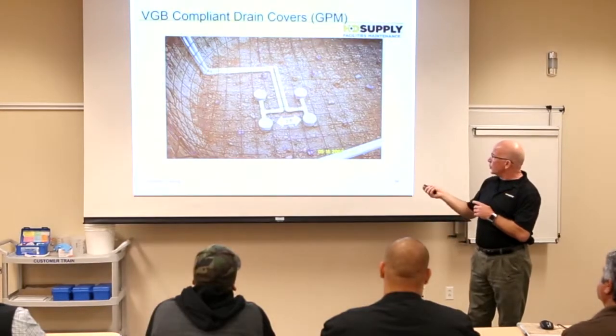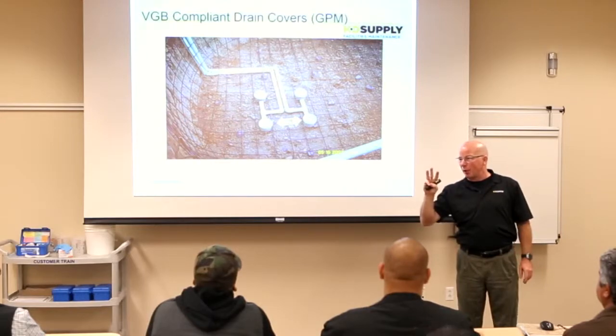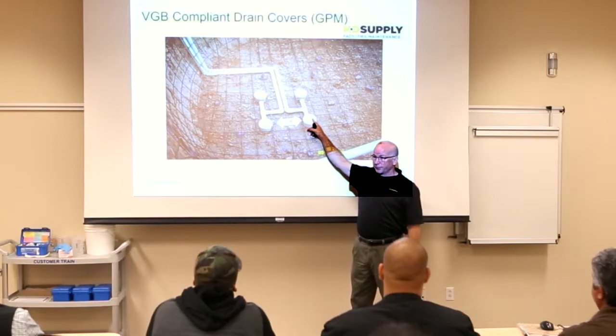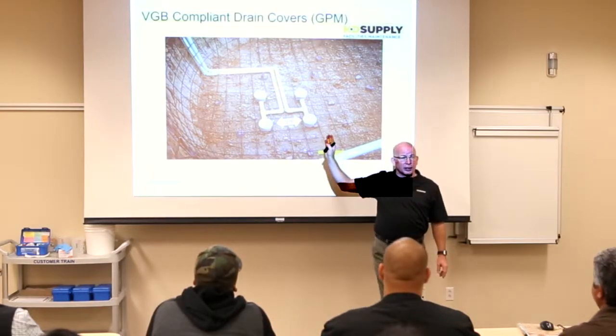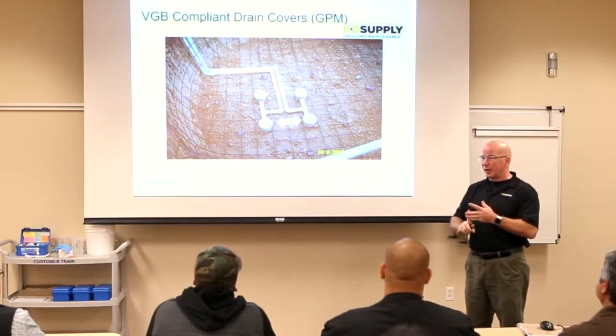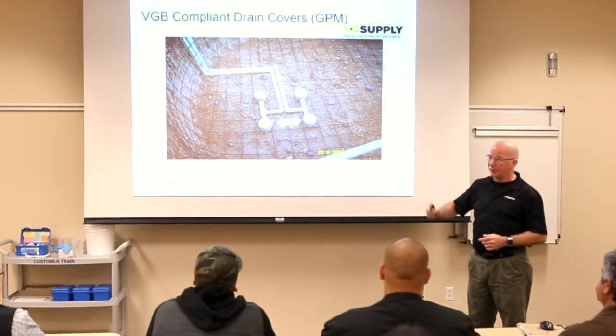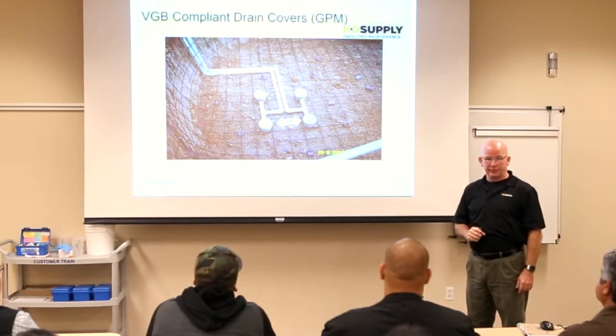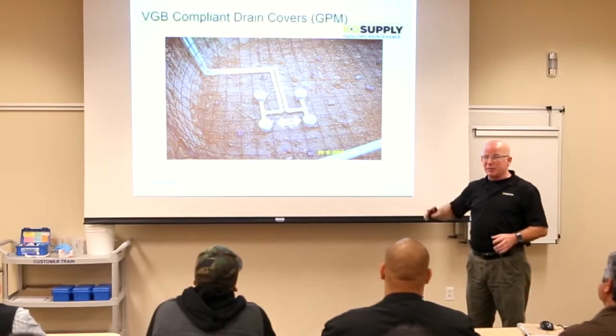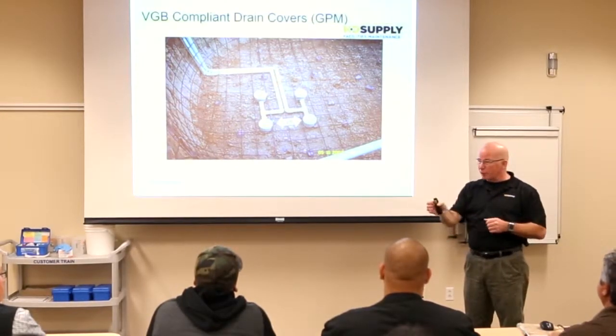On new pools, you have to have multiple main drains at least three feet apart, because you would have to be really big to block two of those at one time. That's the new law. You have to use the compliant covers, watch for anti-siphons and vacuum breaks, and any new pools or ones you dig up in a remodel have to have drains three feet apart. That is what the Virginia Graeme Baker Act requires. If you have specific questions, call your local building inspector to see if yours meets the standard.